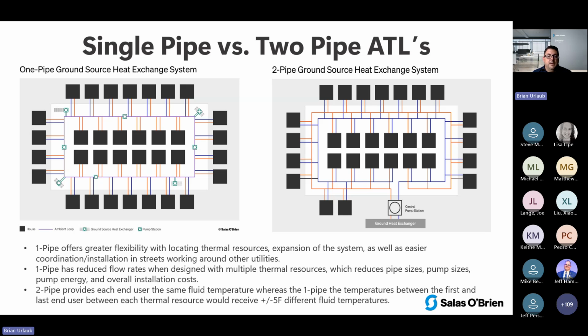Whereas the two pipe system generally has one energy source, delivering the same temperature to all buildings, which is great for them, they all get the same temperature and efficiency. But if the single pipe is done right, honestly the efficiency isn't much different, and I'll show you this in a minute. They'll never know the difference on their bill at 10, 12, or 20 cents a kilowatt, because the efficiencies are so close.